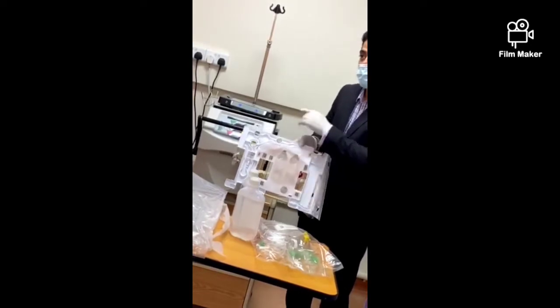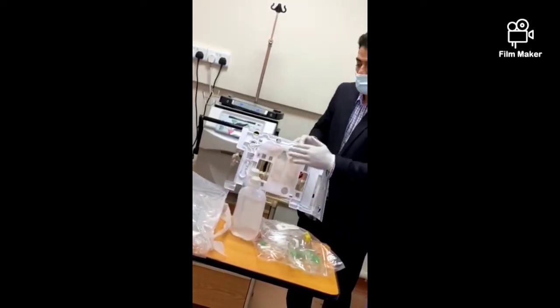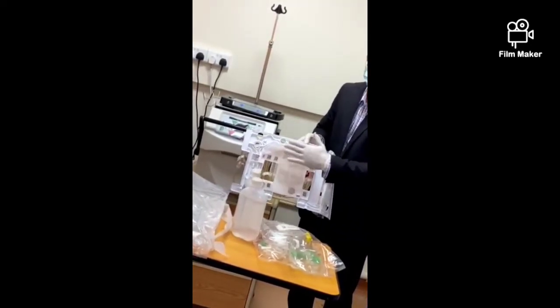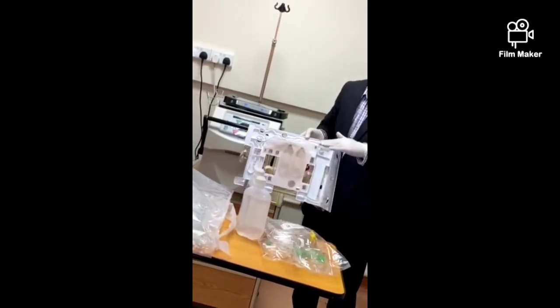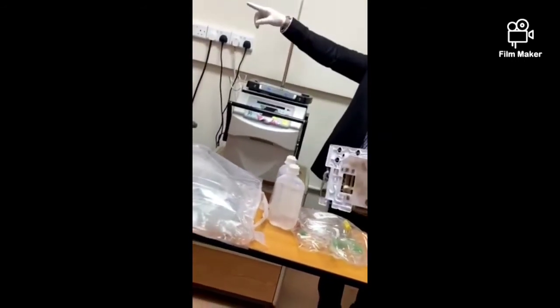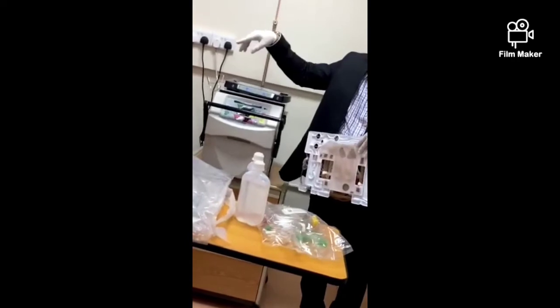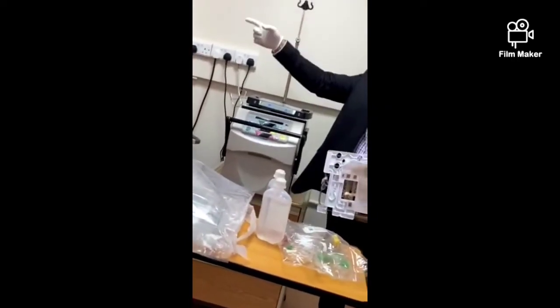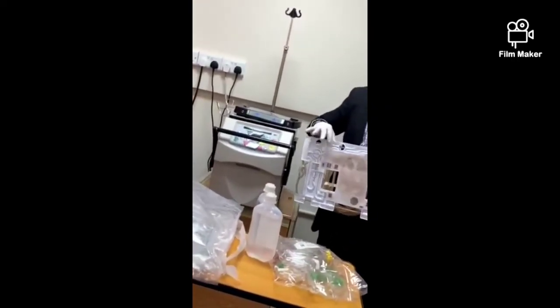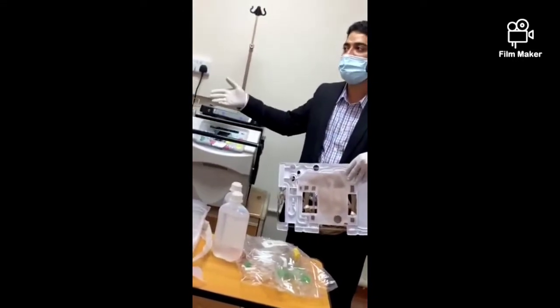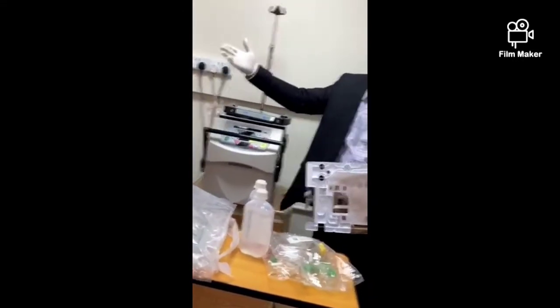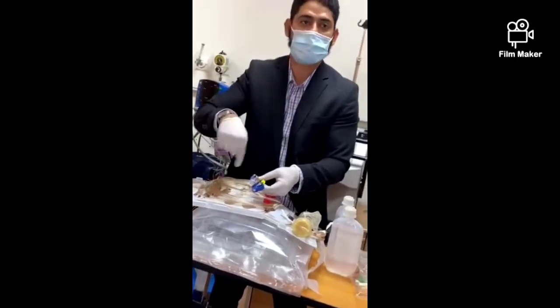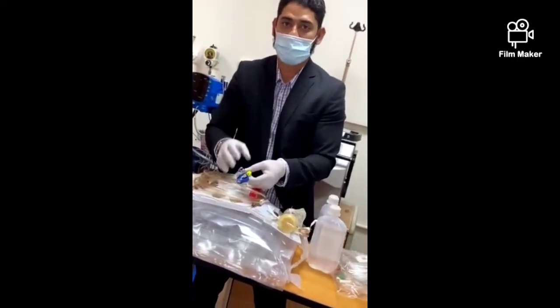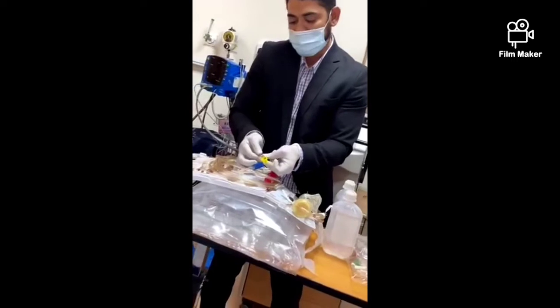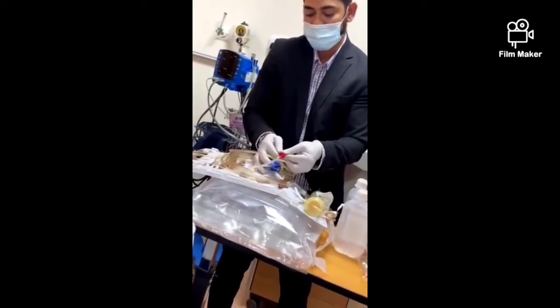So that's why, for this machine, no need for any disinfection. Why? This balance chamber is already attached and disposable. But in other machines, we have the balance chamber inside the machine, so we need disinfection there. Here there is no need for disinfection. Even for hepatitis C, any patient, you can use and transfer. Just need the surface to be clean. Why? Because of the sterilization of this line, it is kept as open end. It's loose. So just tighten it so that there is no trouble for you.